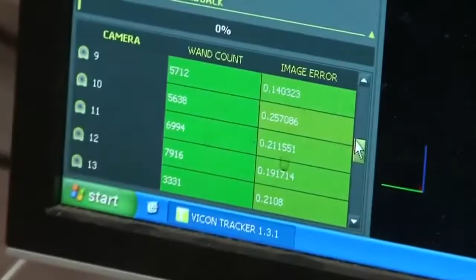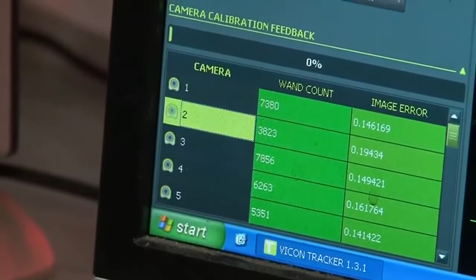And finally, we need to ensure that the air bubbles, the gravitational bubbles, are in the correct orientation, such that down is exactly corresponding with gravity. After this has been done, we can move back to the computer, which has already determined where the cameras are, but not with a given orientation. And so after this calibration has been done and it's completed, we need to look and make sure that the image error is within tolerance. And in general, most of the cameras should be between 0.2, ideally less than that, but definitely below 0.3 in the image error. After this is done, we click Start or Set Volume Origin.